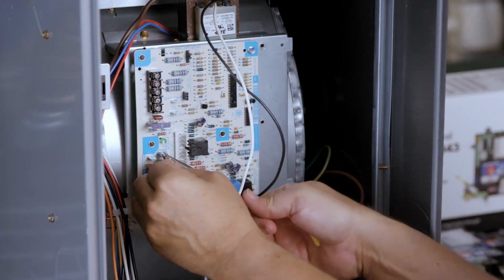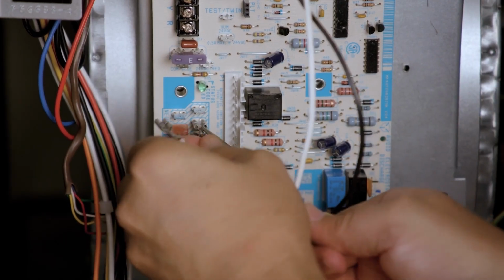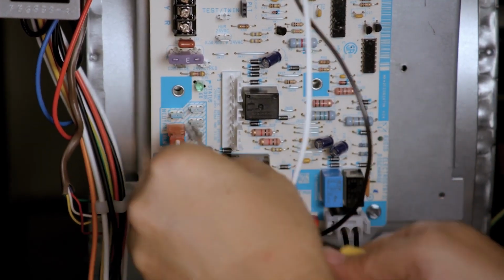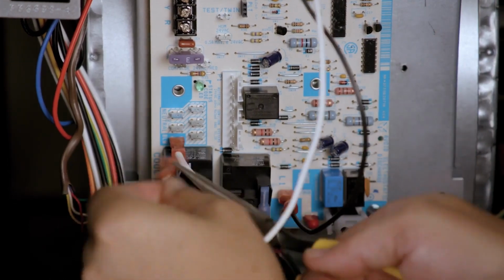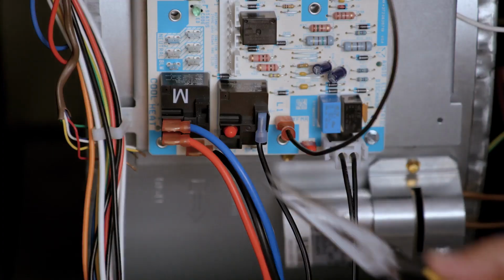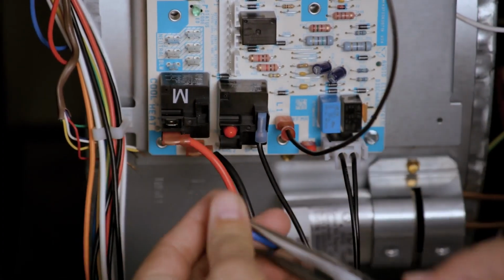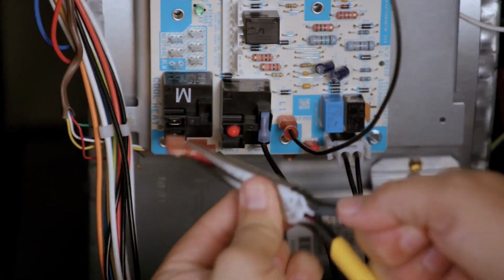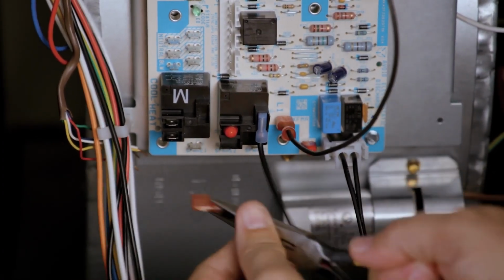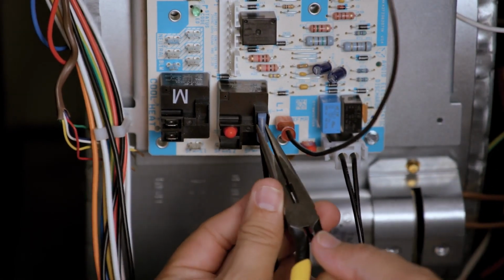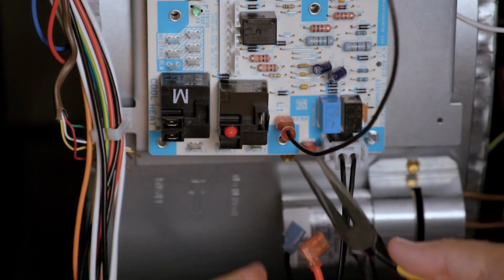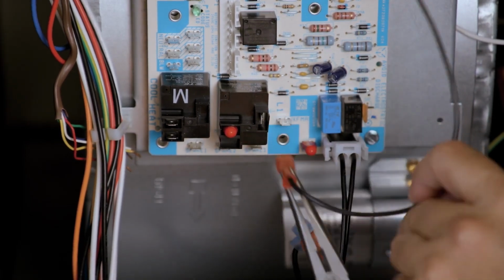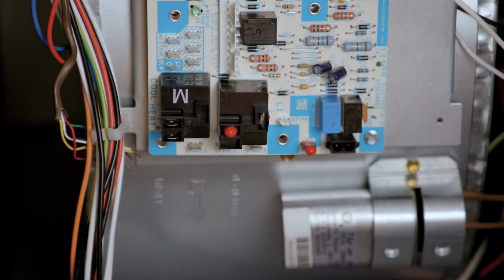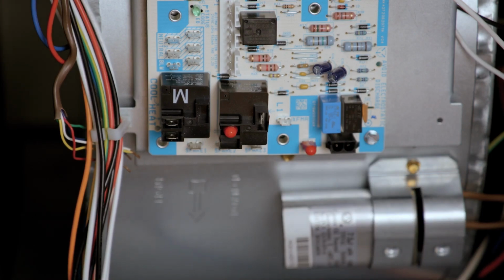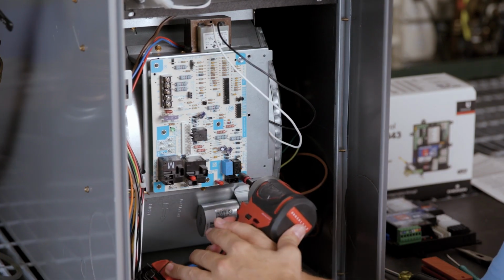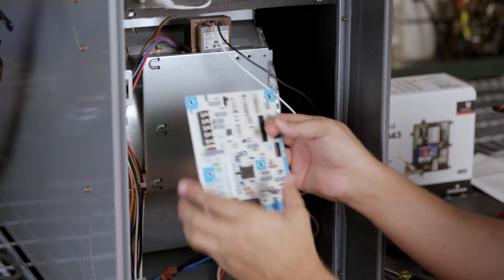Remove the 120-volt neutral wires for the power in, inducer, hot surface igniter, transformer, and blower circulator. Taking note of each color, remove the blower circulator cool speed wire, heat speed wire, and the wire parked on the spare terminal. Remove the 120-volt power in wire. Remove the 120-volt transformer power wire. And finally, remove the 120-volt power plug for the inducer and igniter. Remove the board by unscrewing any screws and disconnecting any standoffs holding the board in place.